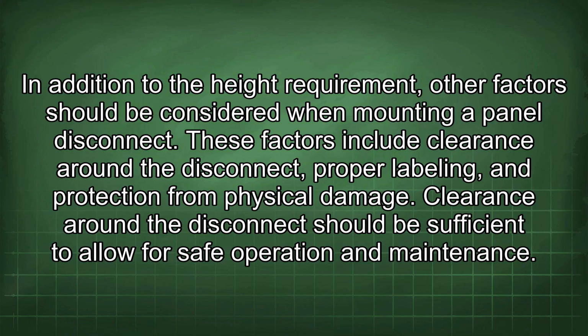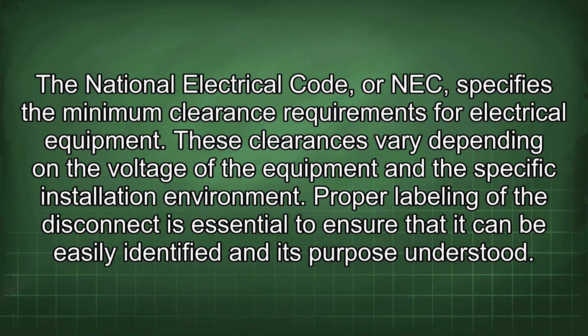In addition to the height requirement, other factors should be considered when mounting a panel disconnect. These factors include clearance around the disconnect, proper labeling, and protection from physical damage. Clearance around the disconnect should be sufficient to allow for safe operation and maintenance. The National Electrical Code, or NEC, specifies the minimum clearance requirements for electrical equipment. These clearances vary depending on the voltage of the equipment and the specific installation environment.